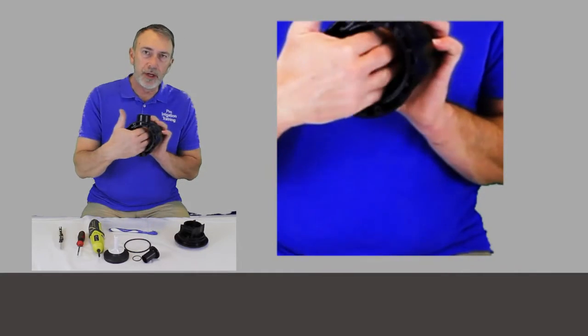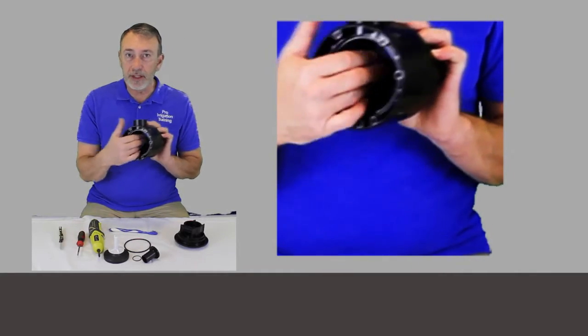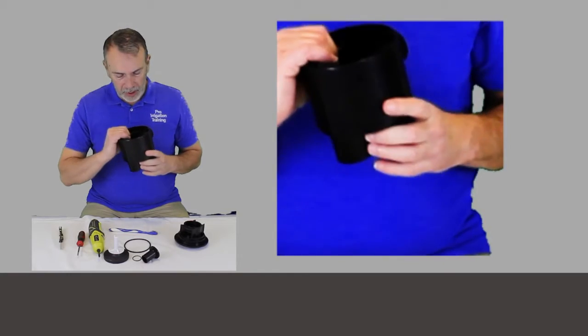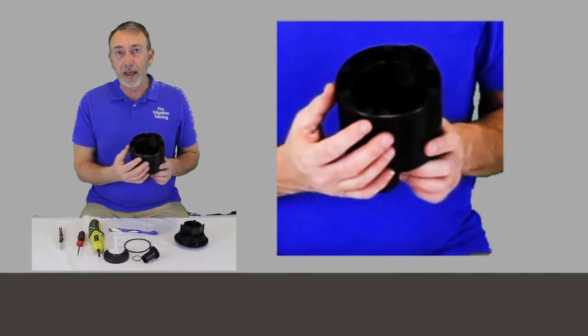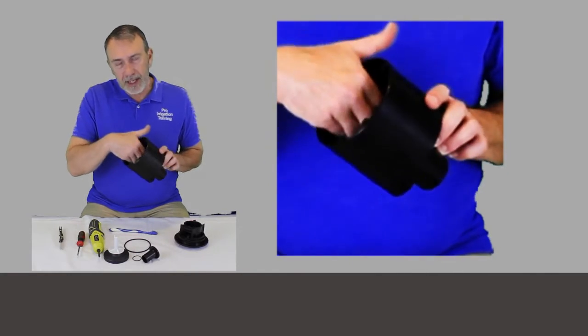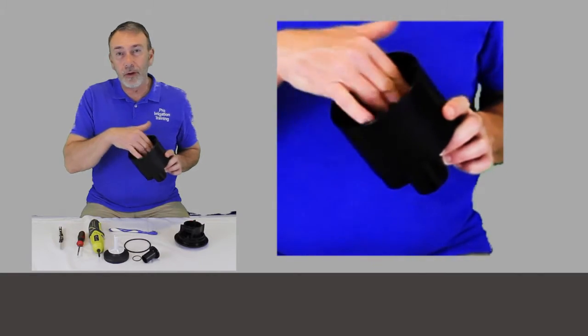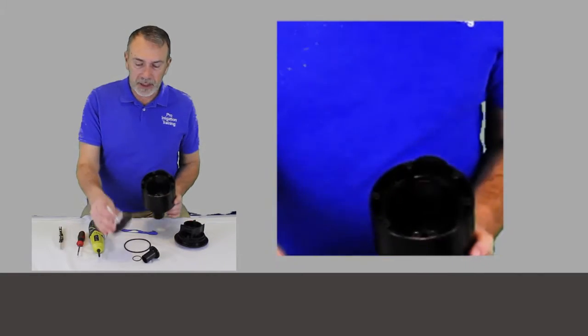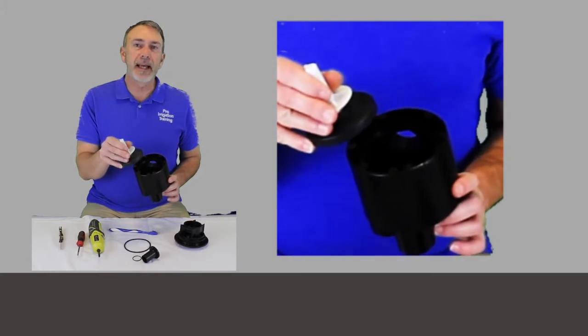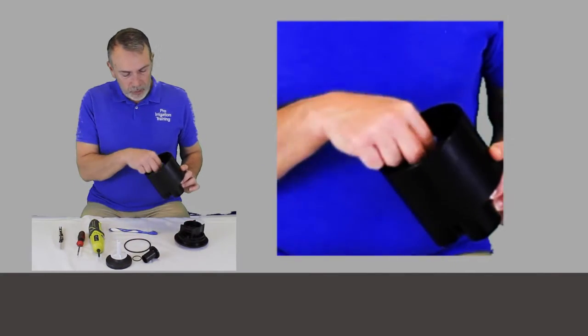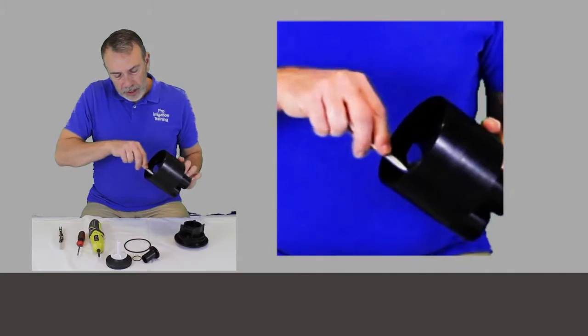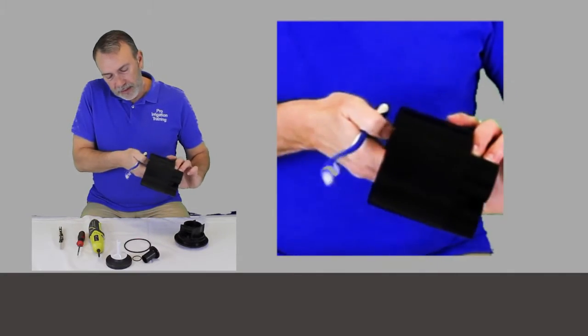But there's also another lip down inside of here, and this is even more important, because it's not just preventing water from leaking out of the case. If this lip down in here has corrosion, scale, or sand on it, it's going to keep this disc from seating down properly. So you want to get down in there and try to make sure that everything's out of it.